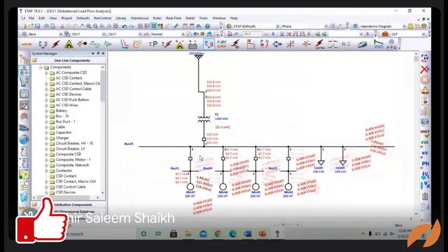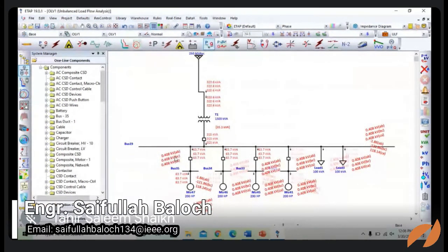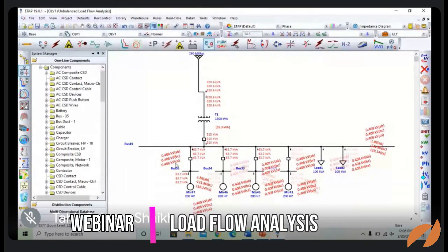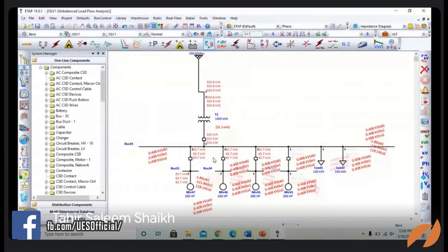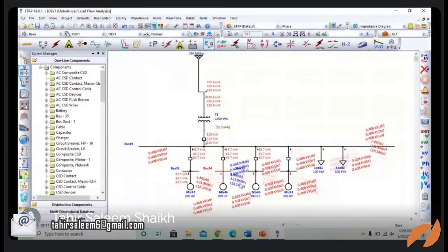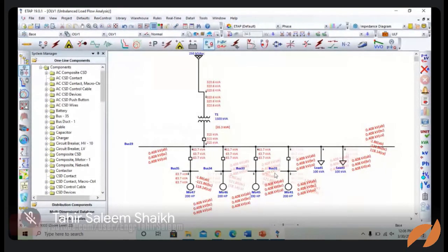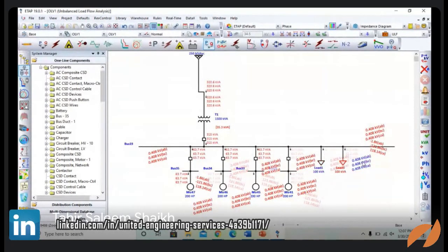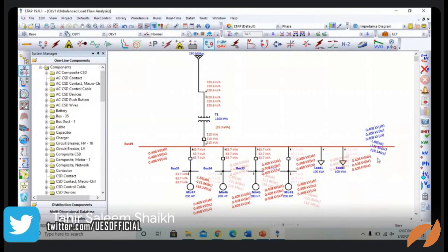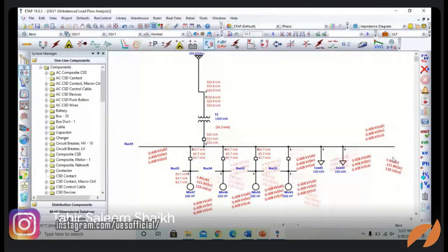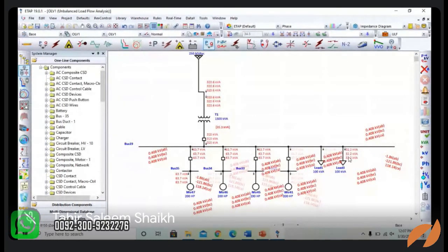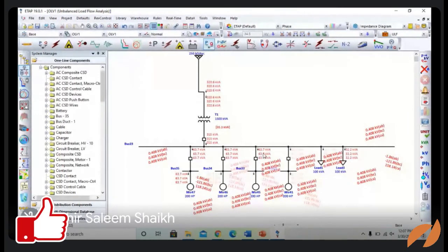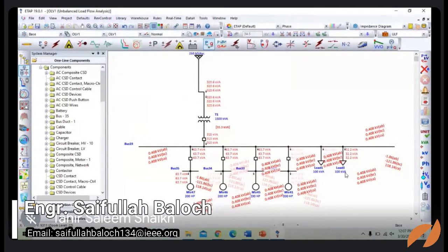Okay, this is the voltages of each phase between AB, BC, CA. So this is the voltages at the terminal of the motor. This is the power flow, same. These are the angles. These are also the angles. So this is the data which you are getting, and this is the bus voltages here, and the bus sequences, bus angles. So as you can see, this power flow in this load is here 32, and the motor is 63.7 kVA. So these are the parameters which you will get in the load flow.